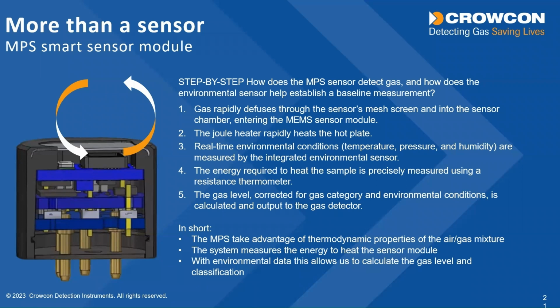And the resistance thermometer is measuring the amount of energy that's taken to heat that hot plate back up to 900 degrees Celsius. And that energy will change depending on the thermodynamic properties of air, because different gases will conduct heat away from the plate at different rates, depending on their own thermodynamics. It also has to factor in real-time environmental conditions, because of course that will also influence the amount of energy needed to heat the hot plate. So there is a temperature sensor, a pressure sensor, and a humidity sensor also on that top PCB that's permanently exposed to the environment. So the sensor system is taking measurements from the hot plate, but it's also taking measurements from those other 3 sensors and factoring them all into the measurement algorithm.